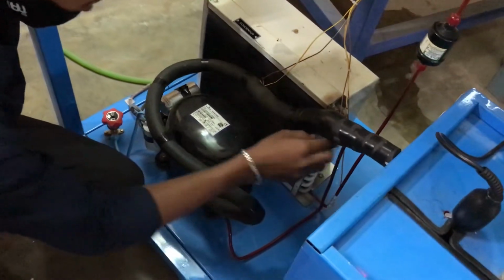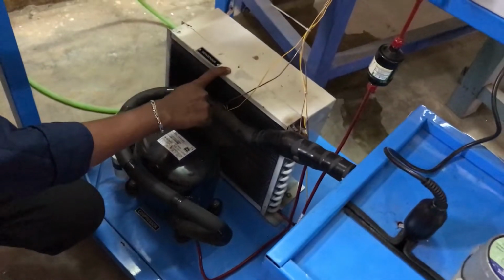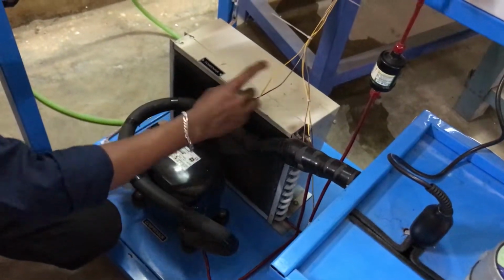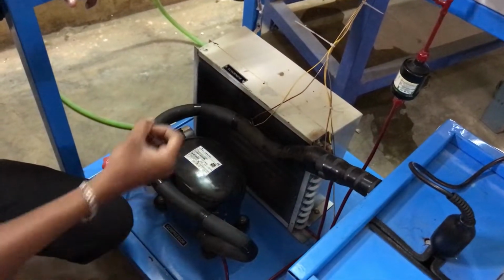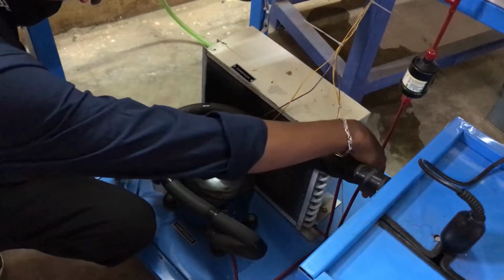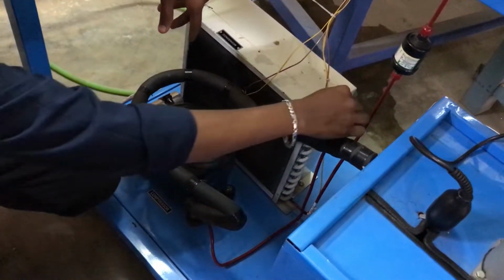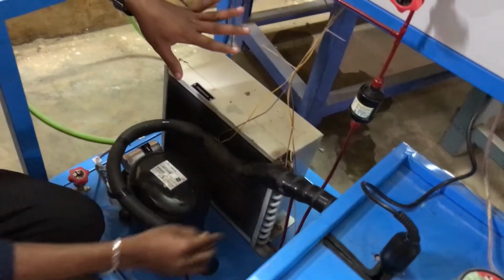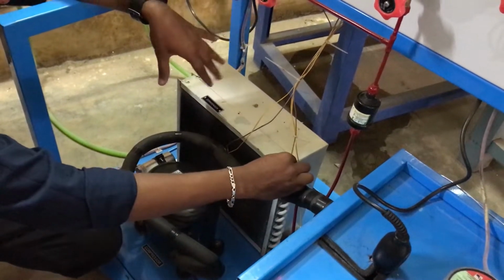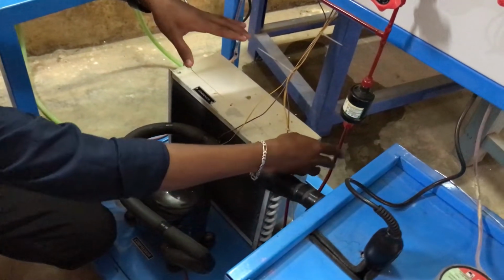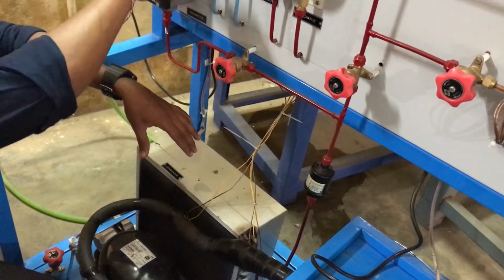Then this will be moved into a condenser. In the condenser, there will be a rotation of the fan. At that time, the pressure will be the same. Then the temperature will be reduced because of the rotation of the fan. That will be removing heat here. So after that, the refrigerant flows here. Another thing here is the change of phase. It happens because here it is gas. Because of the removal of heat, the refrigerant changes phase from gas to liquid here. So we can see it directly here.